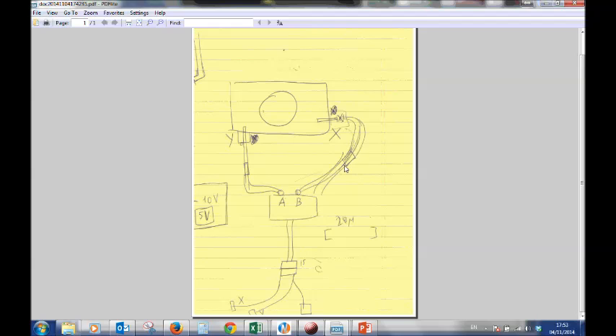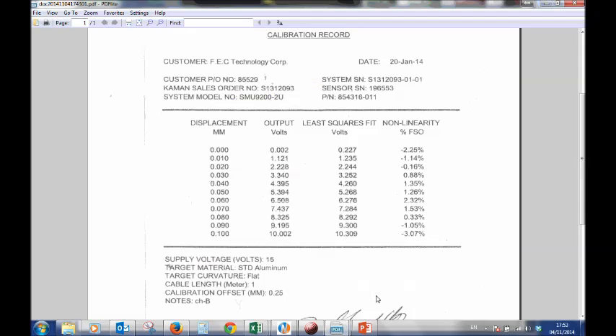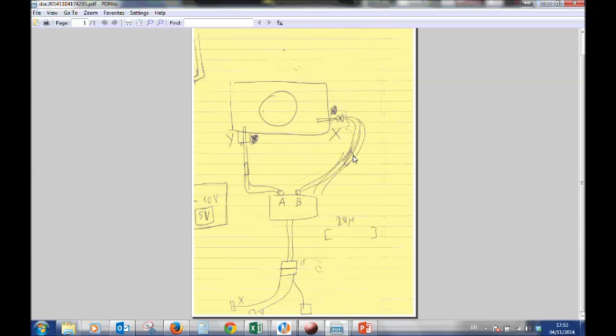There's a number on each cable, and if we look at the data sheet of the sensors, it will say here sensor serial number. There's a certain number here, and the channel. So we have to make sure that this number is connected to this channel. Okay, so the number which is written here is connected to the correct channel.